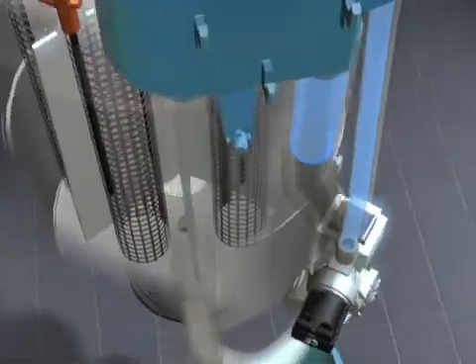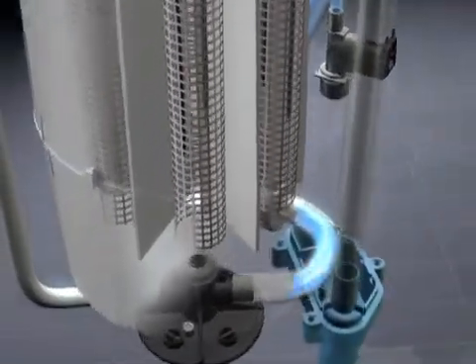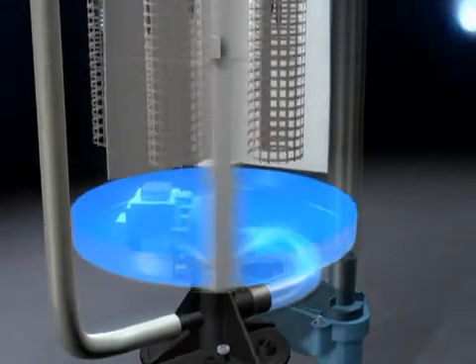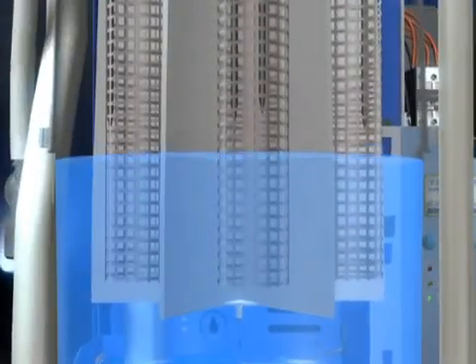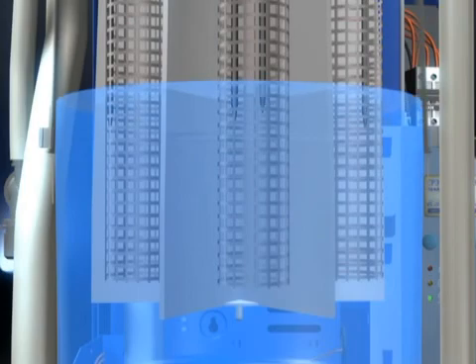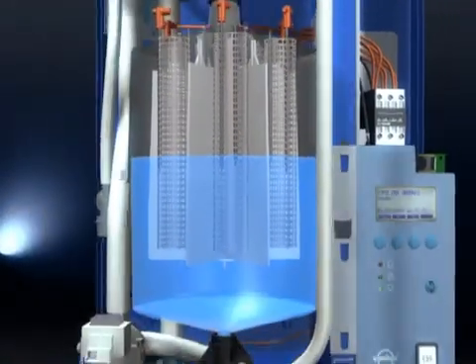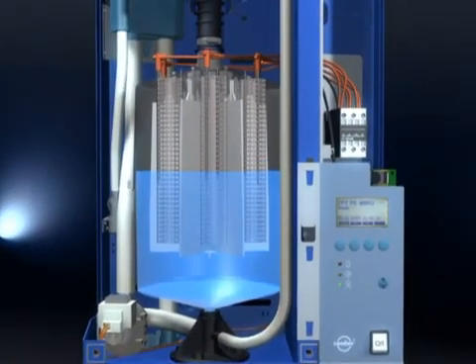The water flows into the steam cylinder, passing through the inlet hose and the water cup. The water makes contact with the electrodes and steam production starts. The principle is simple. Water conductivity causes the electrical current to flow and thus provides proportional steam extraction.